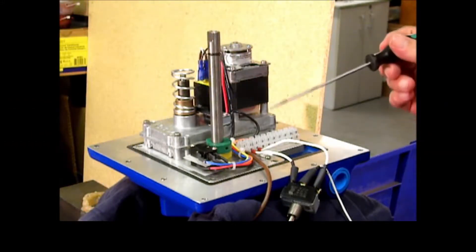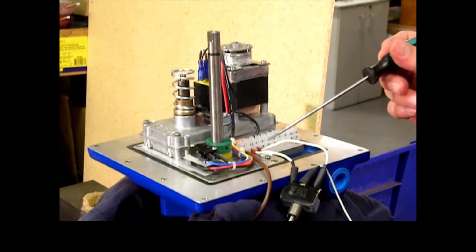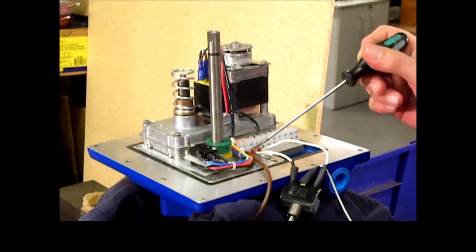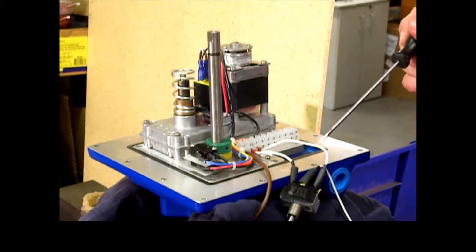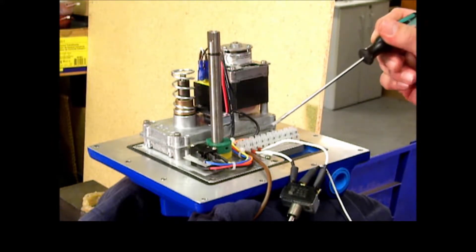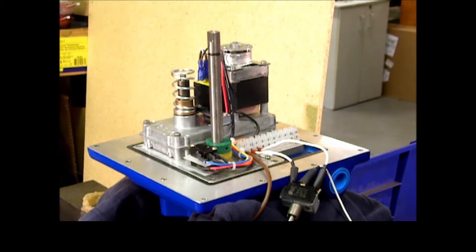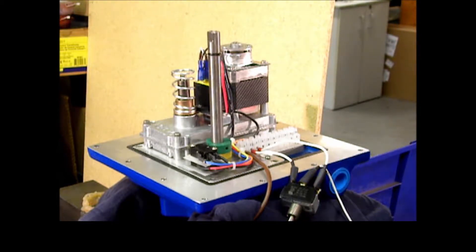This is a two wire system. You have 120 volts, your neutral line runs into pin 1, and then your hotline is split to go to pins 2 and 3 through either a single pole double throw contact on a relay or some type of a control switch that is also single pole double throw.